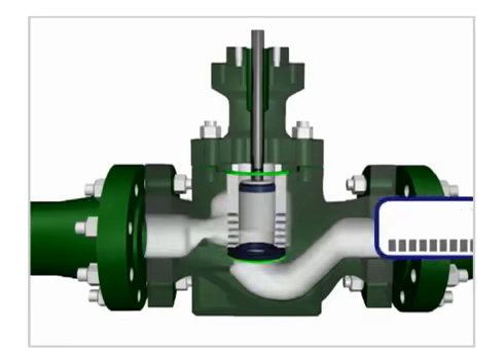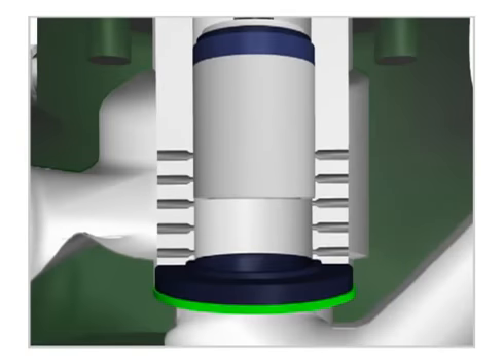Cavitation is isolated by directing fluid into the center of the valve using a flow down orientation so bubbles implode away from the valve components.